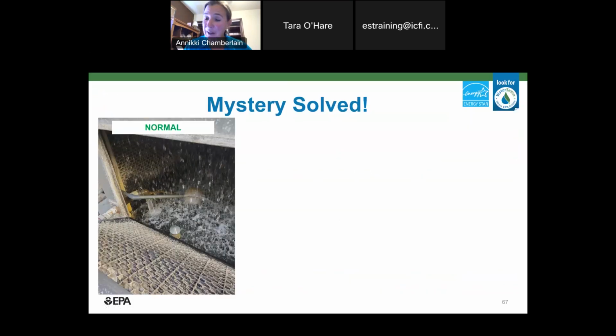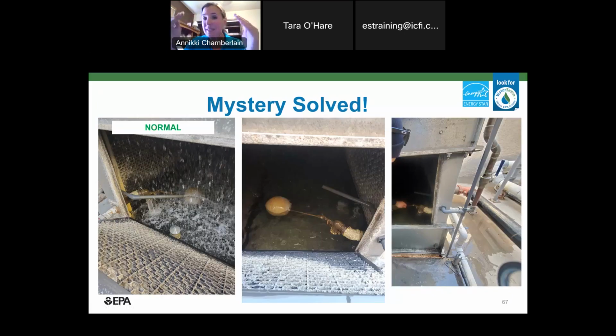What we were able to figure out was this. You can see the overflow valve right here and the makeup valve. The chiller was coming on and off all the time. When the chiller would shut off, all the water would drain out of the tower and cause overflow. Then when the chiller would come on, it would do this huge suck of water out of the tower and start to cavitate the pump. That was the big spike of water. Then the chiller would run, shut off, drain all the water, overflow the tower, come back on, do that big drain. So we're both a waste and an asset damage event.